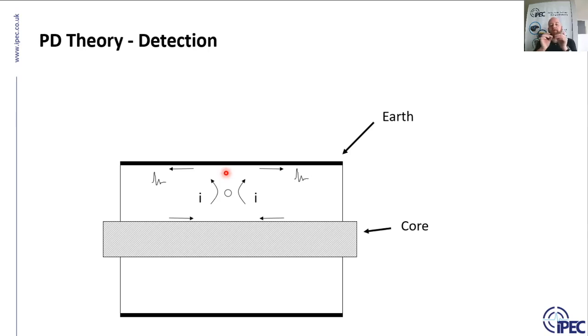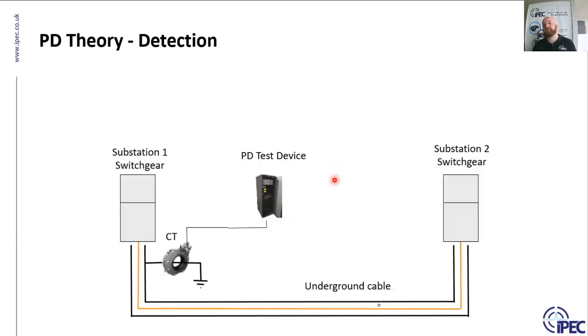But what happens is they will travel away from the PD source along the core and along the earth. Now again, I must emphasize with all PD signals, these are high frequency signals, so it's not high current, it's not a load traveling along the cable, it's a high frequency, very fast moving signal. So this high frequency signal is traveling along the inside of the cable, and if my animation works this time, there we go, it will travel along the inside of the cable earth in our example, come out at the switchgear and through the HFCT.